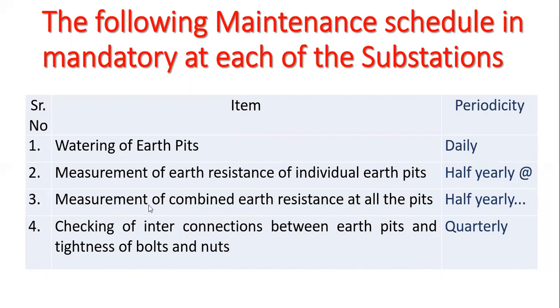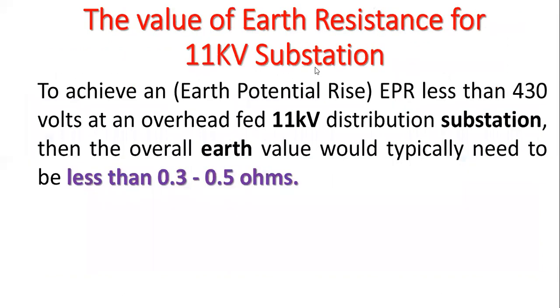The next, third point is measurement of combined earth resistance of all the pits, that you have to measure twice in a year. That means half yearly you have to measure the combined earth resistance of all the pits. Then last is checking the connection between earth pit and the tightness of the bolt and nut. So you have to check quarterly the connection between the earth pit and the tightness of the bolt and nut. So these are the maintenance tasks which are mandatory in case of your earthing system, in case of your substation.